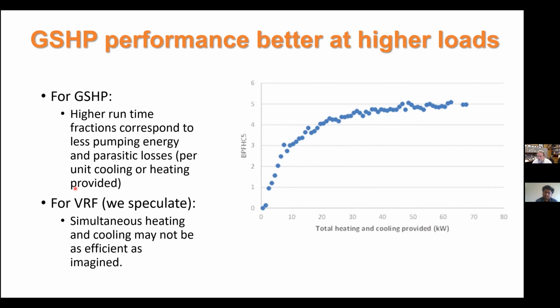The same thing was true for the VRF system. This is some speculation based on some other research that's been done: simultaneous heating and cooling is often advertised to be one of the great features, but it may not be as efficient as imagined. If you're going to provide heating and cooling, the refrigerant temperature in the condenser has to be higher than it might be otherwise, and that's maybe not as efficient as imagined. But I say it's speculation. We don't have those kinds of measurements for the VRF system.